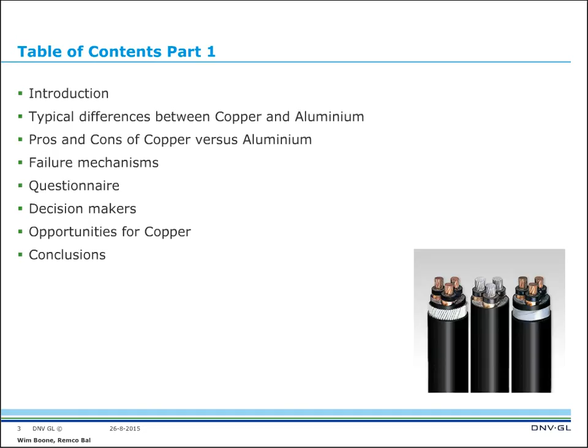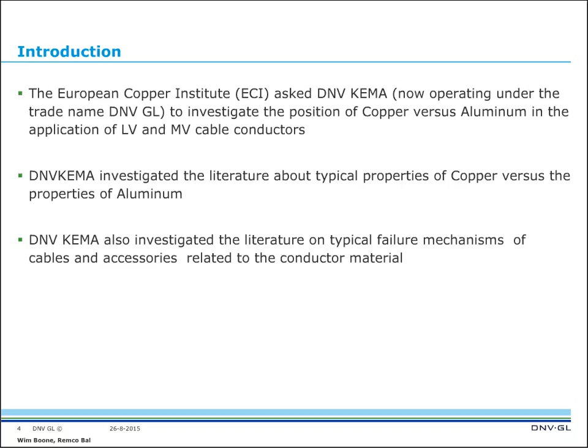The European Copper Institute asked DNV KEMA, now operating under the trade name DNVGL, to investigate the position of copper versus aluminium in application of low voltage and medium voltage cable conductors. DNV KEMA investigated the literature about the typical properties of copper versus aluminum, and also the typical failure mechanisms of cables and accessories related to the conductor material.